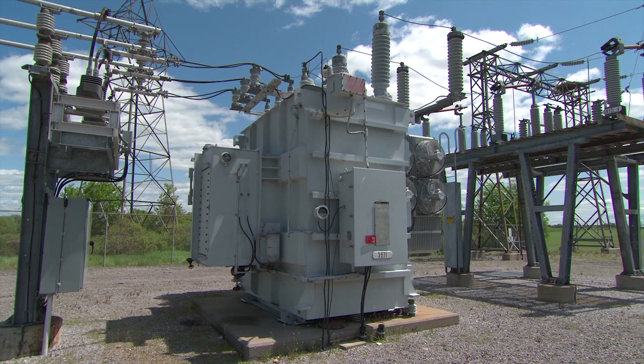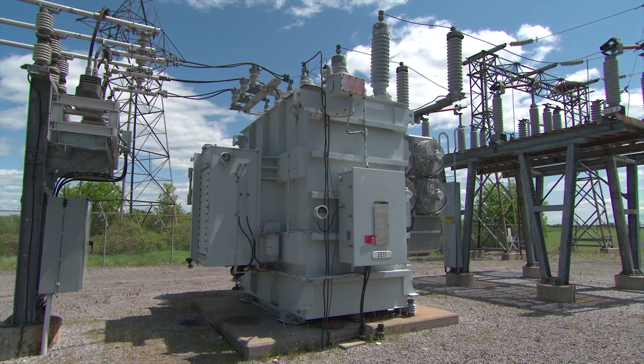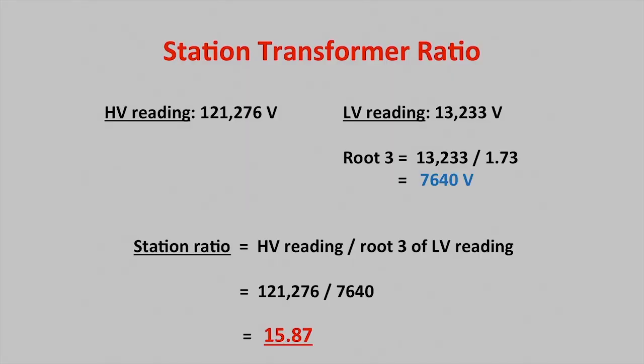Because this station has a delta star transformer, the phase to neutral voltage is root 3, 1.732, of the phase to phase voltage, which equals 7,640 volts. That's 13,233 divided by 1.732 equals 7,640.